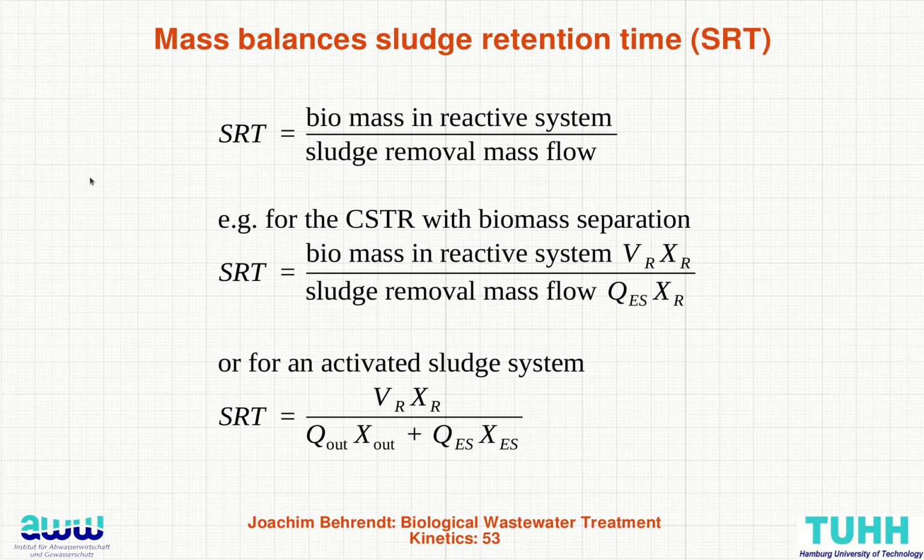But now we want to come to the sludge retention time, which is a very important measure. So finally, the sludge retention time is the biomass in the reactive system, also in our reactor, where the reaction takes place, with respect to the sludge removal mass flow. Also this is in kilograms per day, and this is finally kilograms, and finally there comes out a time, also the sludge retention time.